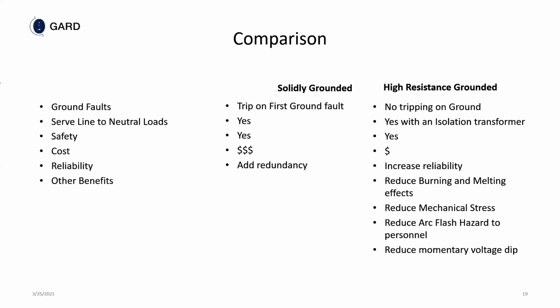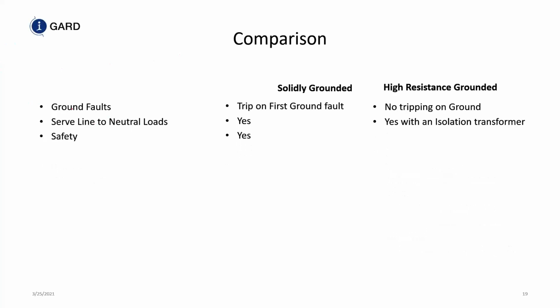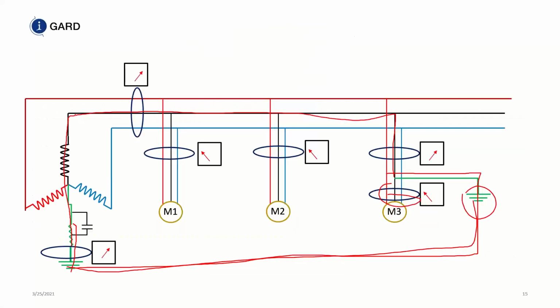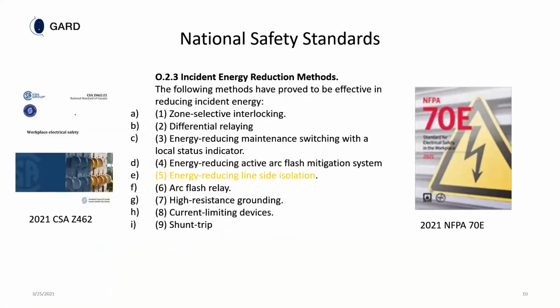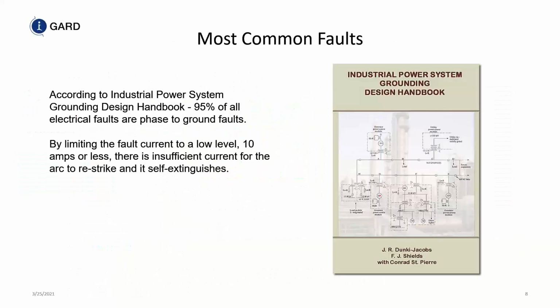It has nothing to do with phase to phase current. But remember that book I showed you earlier? That book says that up to 95 or 98% of all faults begin as single phase to ground faults, and then they propagate to phase to phase or three phase faults. So much so that they're saying 98% of all faults are single phase to ground type, 1.5% or 1% are phase-to-phase faults, and 0.5% of all faults are three-phase bolted faults.